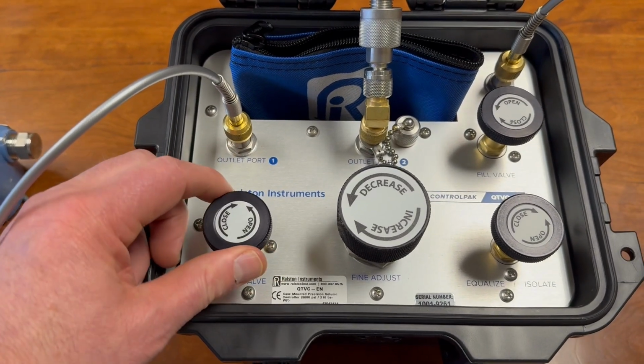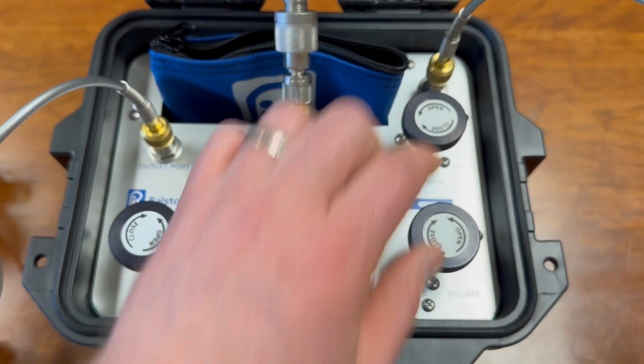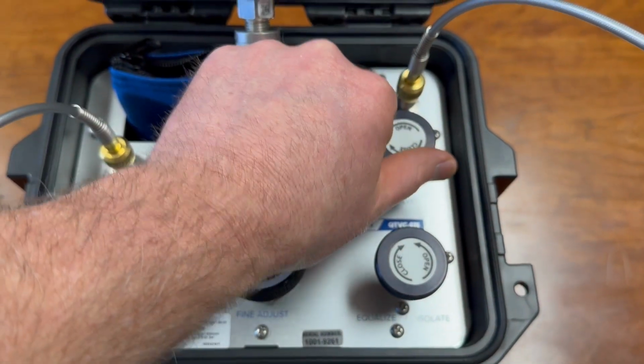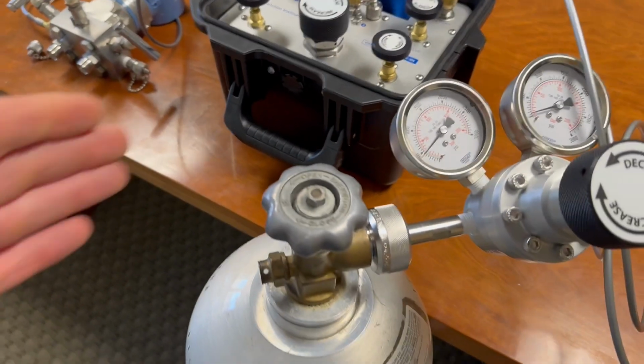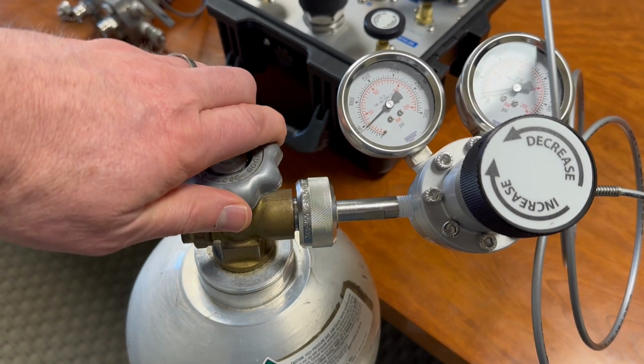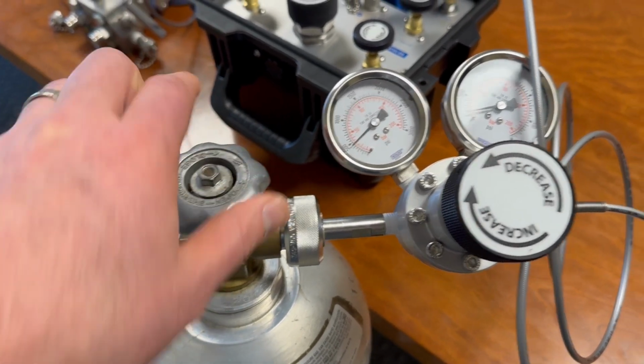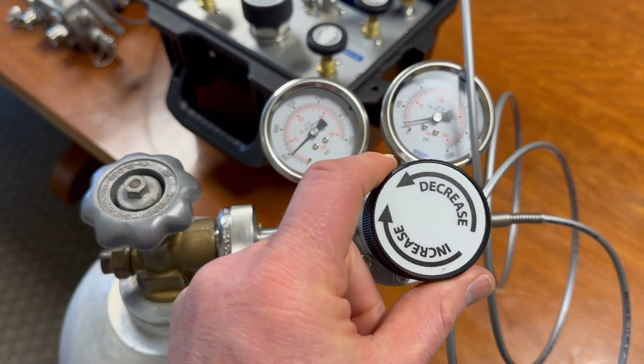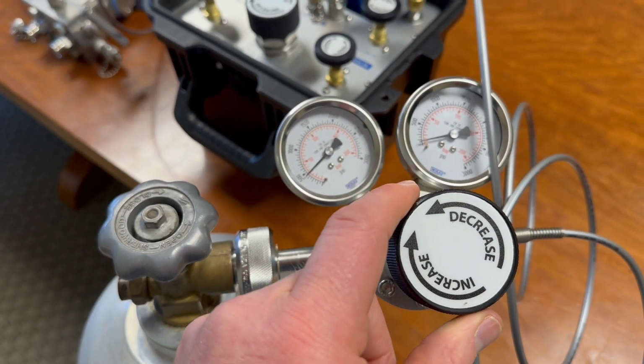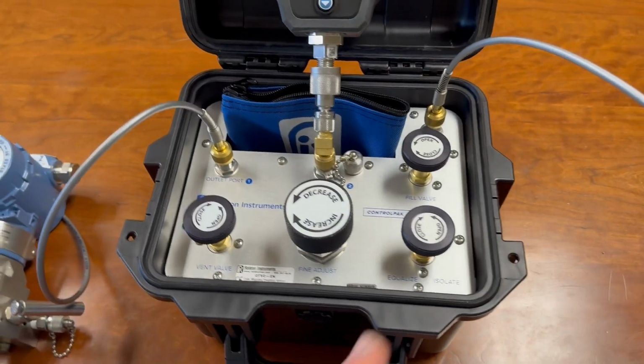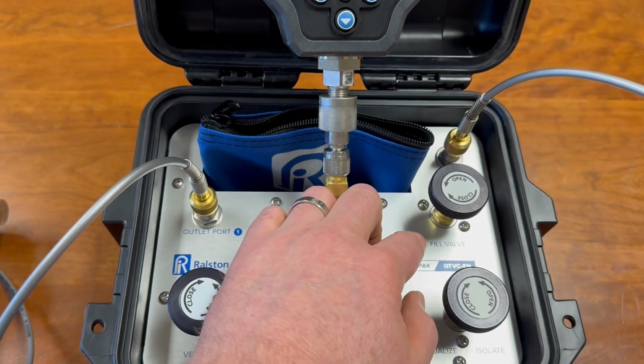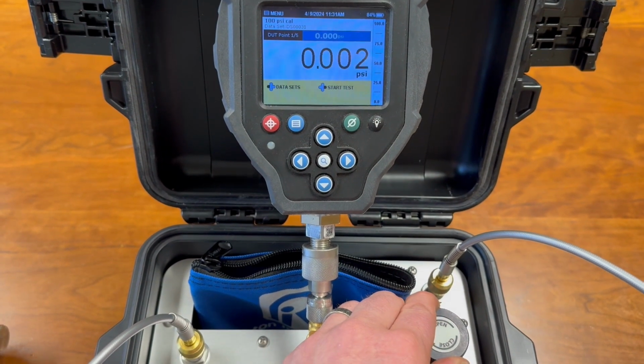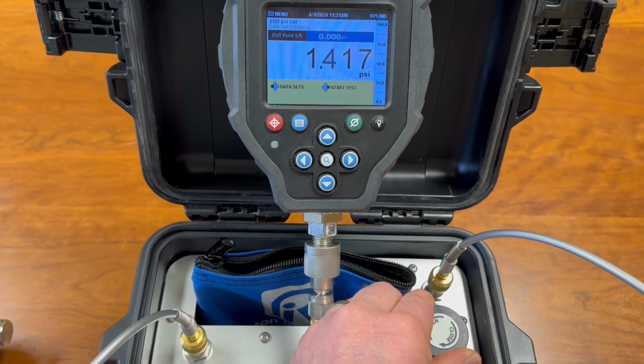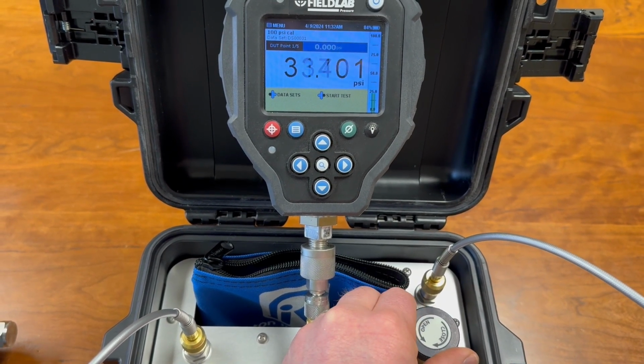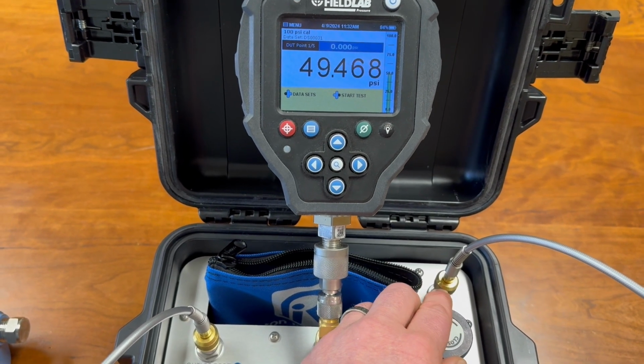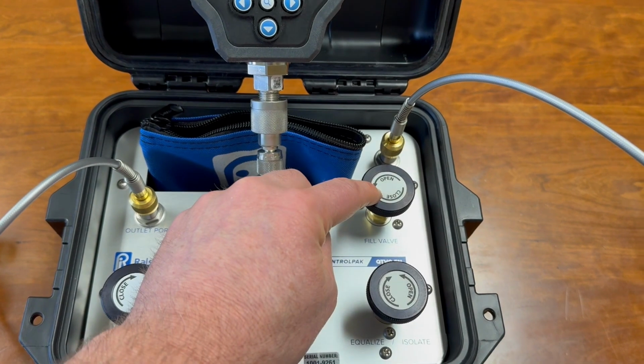Okay, so the first thing we want to do before we get started is close the vent valve here. We want to open the equalize valve here, and then close the fill valve. Next, we're going to bring our regulated pressure into the system. So we're going to open this valve, and our regulated pressure is going to come up, and then we're going to increase the regulated pressure until it's approximately at our first test point. When that's done, we're going to bring in some pressure using this fill valve. You can see here as I open this valve, we're going to bring it up to our first test point, which is 50 psi. So this is a nice metering valve. We can bring up pressure nice and slowly. After we're close, we're going to close that fill valve again.